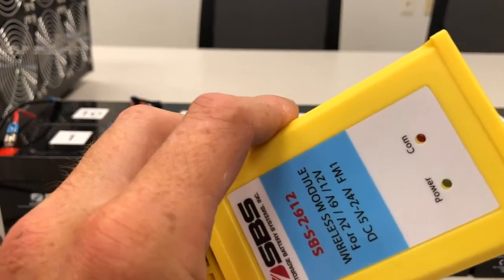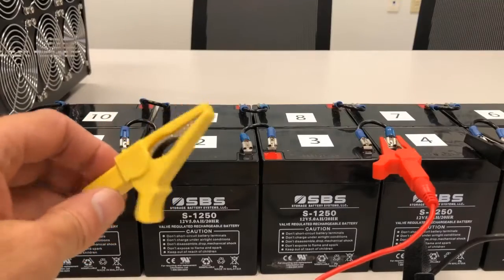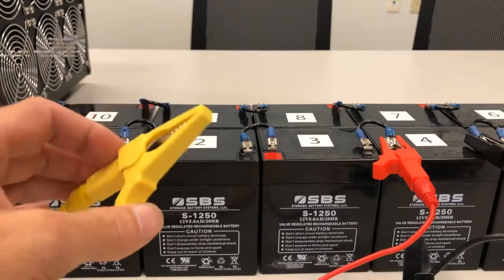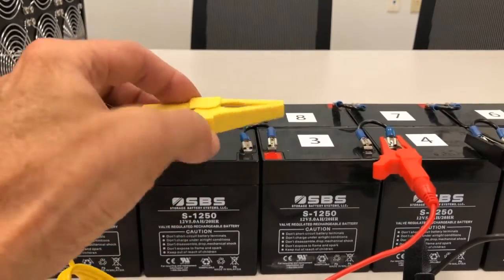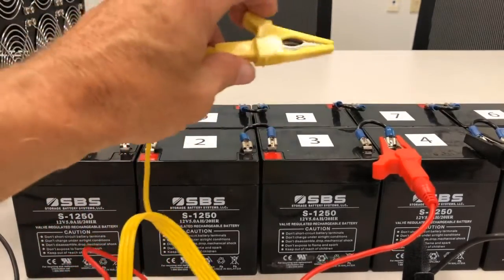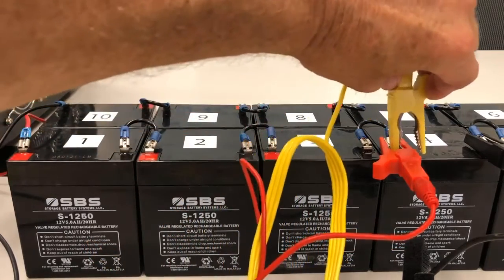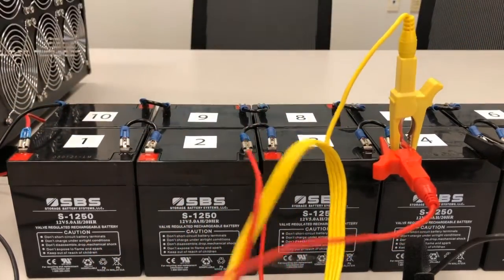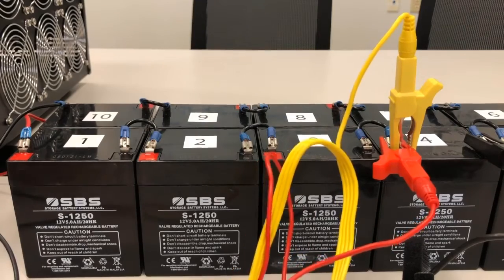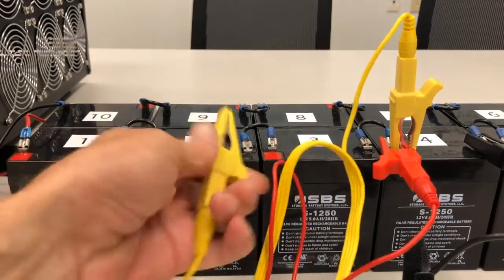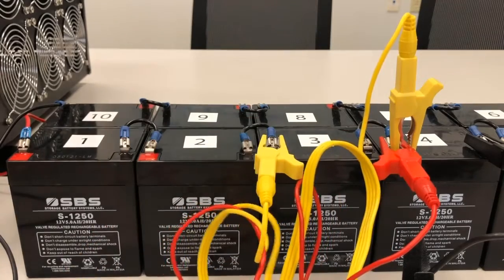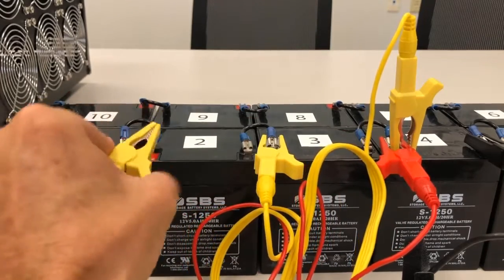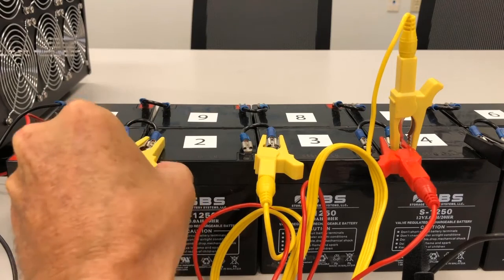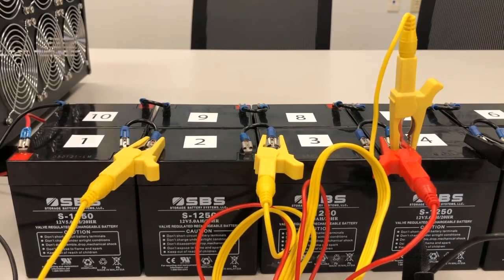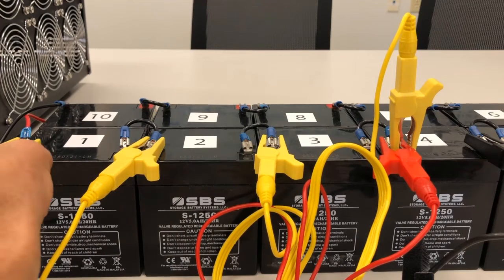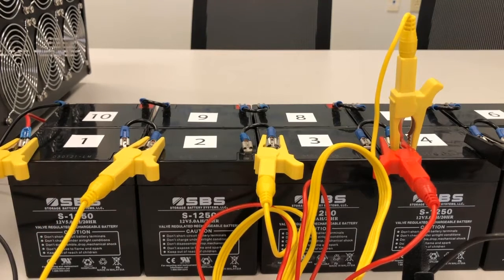The 4 yellow leads for the wireless modules connect to the batteries in order, with the shortest yellow lead being the closest to the black lead. The next longest yellow lead goes to the positive of battery number 3. The next longest yellow lead goes to the positive of battery number 2. And the longest yellow lead goes to the main positive of the battery string.